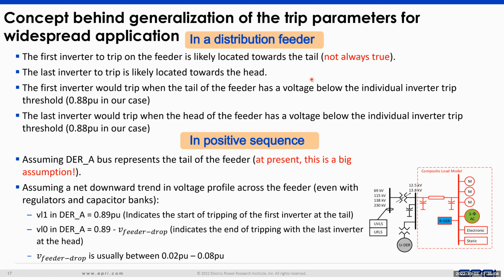The first inverter would trip when the voltage is below the trip threshold, in our case 0.88 per unit at the tail end. The last inverter would trip when the voltage is below the threshold at the head of the feeder.